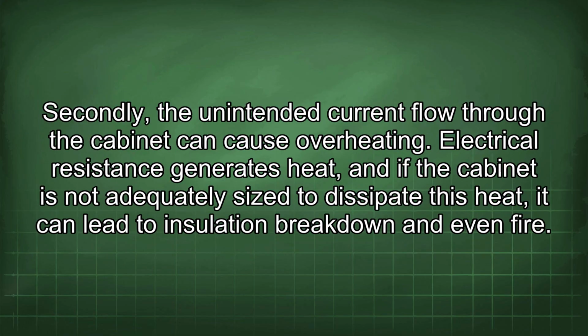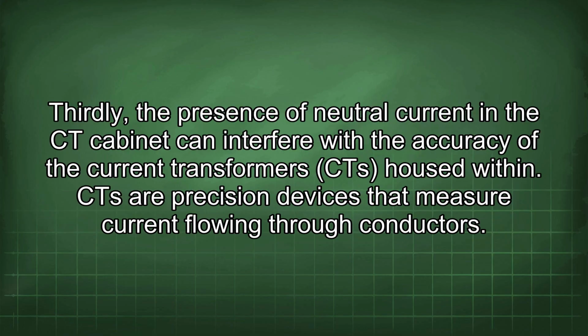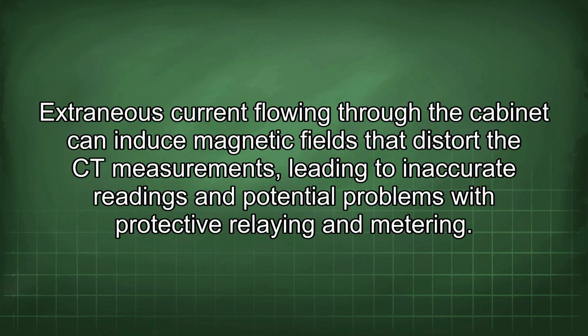Secondly, the unintended current flow through the cabinet can cause overheating. Electrical resistance generates heat, and if the cabinet is not adequately sized to dissipate this heat, it can lead to insulation breakdown and even fire. Thirdly, the presence of neutral current in the CT cabinet can interfere with the accuracy of the current transformers (CT) housed within. CTs are precision devices that measure current flowing through conductors. Extraneous current flowing through the cabinet can induce magnetic fields that distort the CT measurements, leading to inaccurate readings and potential problems with protective relaying and metering.